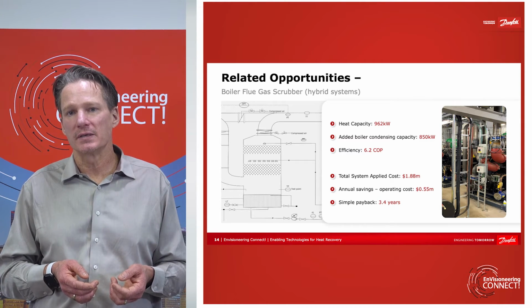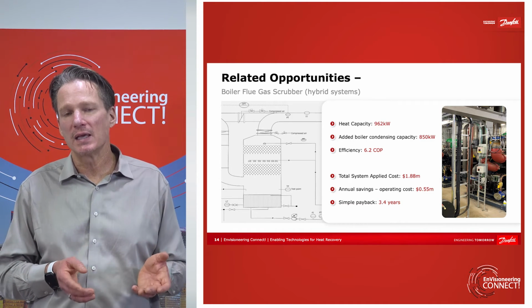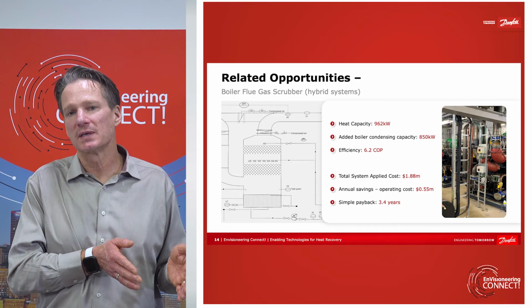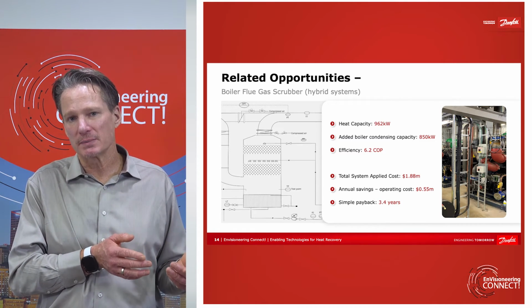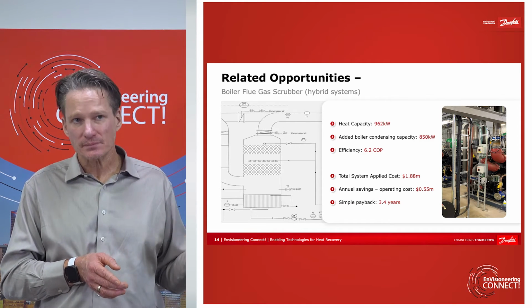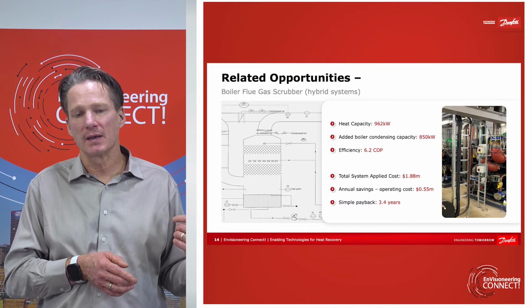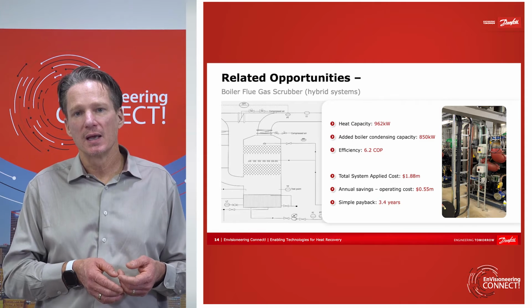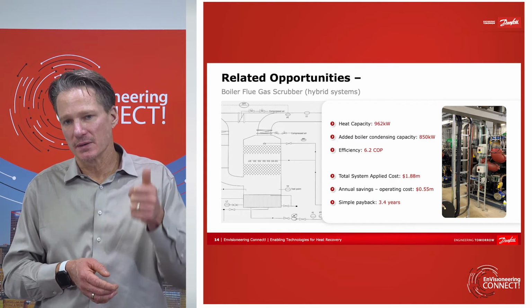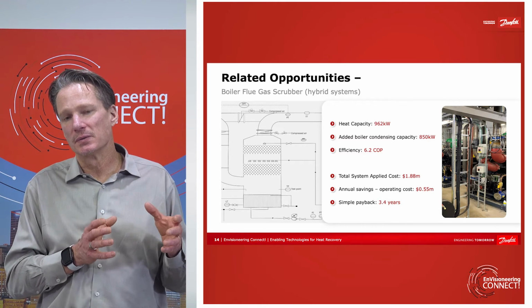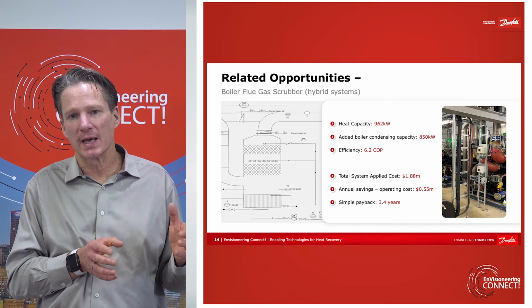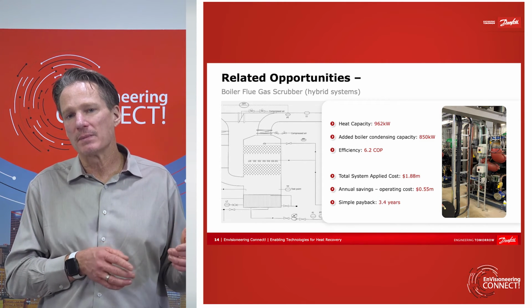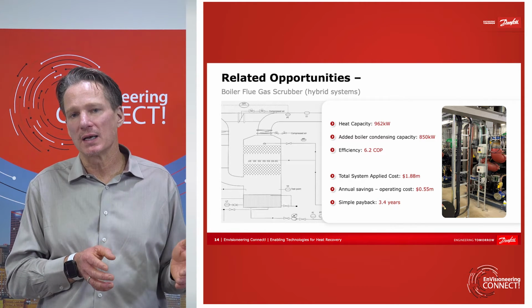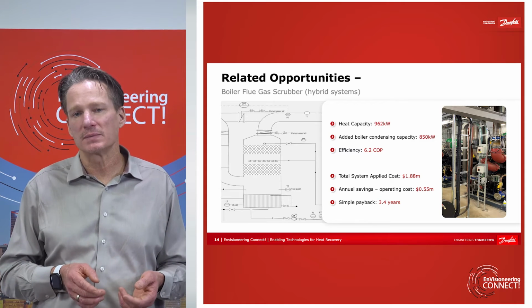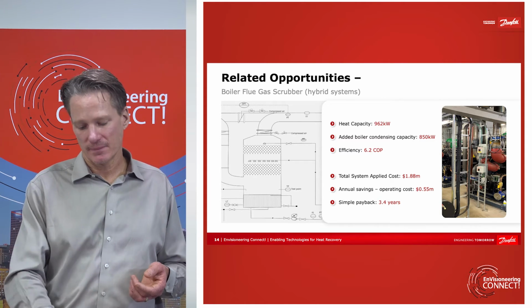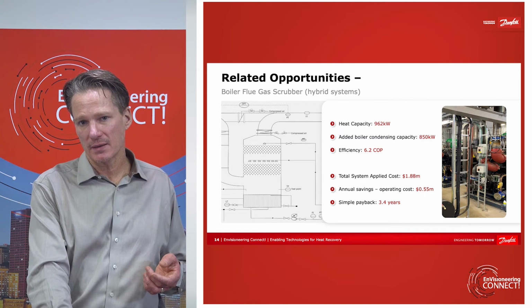This is an example of one in a district heating utility that we worked on to recover the heat from the flue gas scrubbing from another heat source. In this case, it was biomass. So they were actually burning wood chips, and that heat was then going into a boiler to create heat for the district energy grid. And that boiler exhaust was then coming off and going into the air. And so they wanted to add a scrubber system on it to scrub out the contaminants coming from that exhaust, but also then to recover the heat from that exhaust system. And so this sprays water over that exhaust, and then recovers the heat via the water-to-water heat pumps that we applied to the district energy system as well. So supplementing that heat provided by the biomass system.